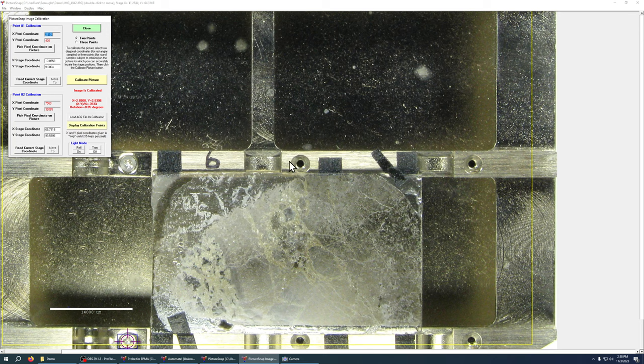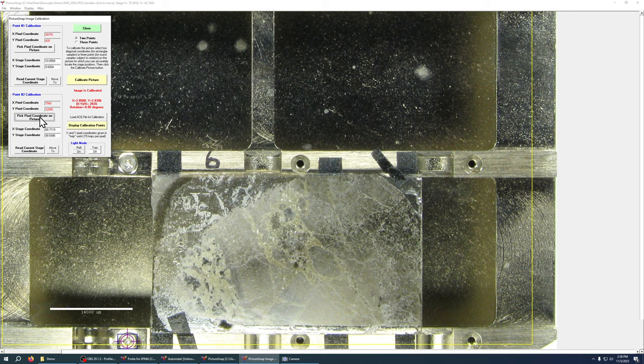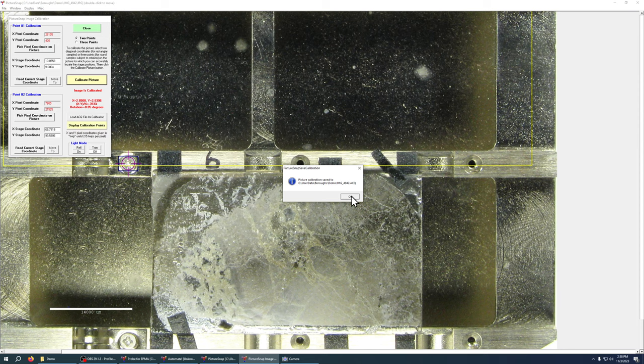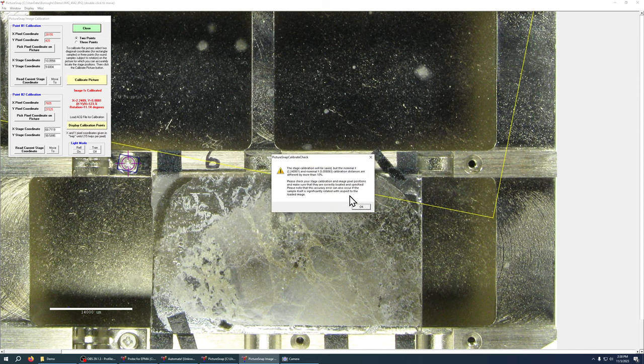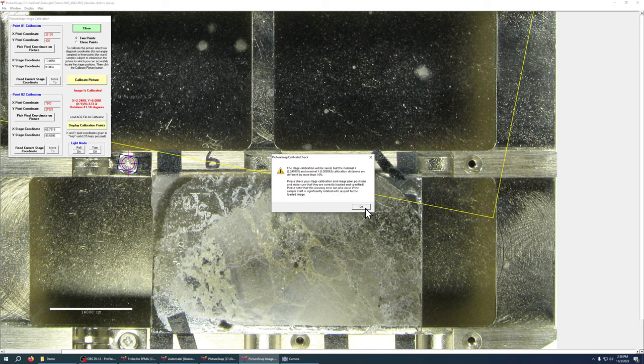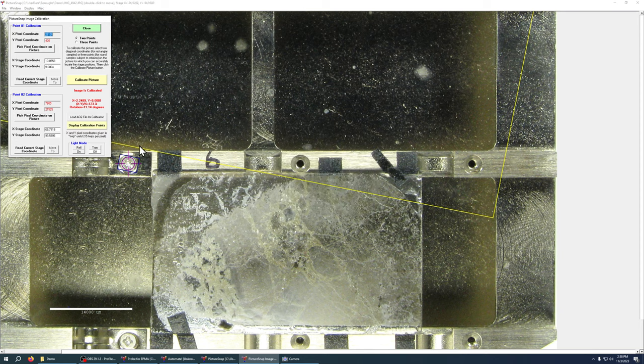Just a note if you do make a mistake for instance one of the common mistakes I have with my holder is I'll accidentally pick this screw instead of this screw if I'm not paying attention. You can just start over so I'll show you what happens. So I'm going to pick my pixel coordinate again, click it there and hit calibrate picture. It does the calibration but now you can see that it's throwing a warning, it's saying something's probably not right here, your calibration distances are greater than 10 percent. It's basically saying check your work here and you can see this yellow line that is what PFE thinks is the stage limits and you can see that's obviously screwed up.